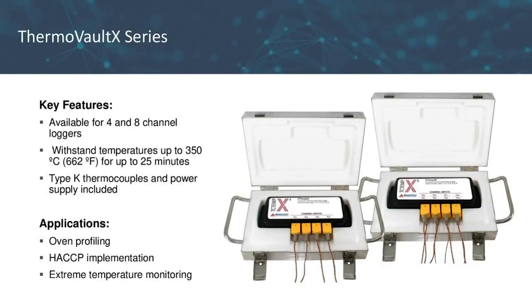One addition worth mentioning is that the 4 and 8 channel TC-TempX loggers are compatible with our ThermoVault system. For those unfamiliar, this is a thermally insulated, thermocouple-based temperature logging system that can withstand temperatures up to 350°C for up to 25 minutes when properly sealed. Included in this system are Type-K thermocouples as well as a power supply. The stainless steel enclosure and external thermocouples provide accurate temperature measurements and fast response times. Application examples include oven profiling, HACCP implementation, and extreme temperature monitoring.